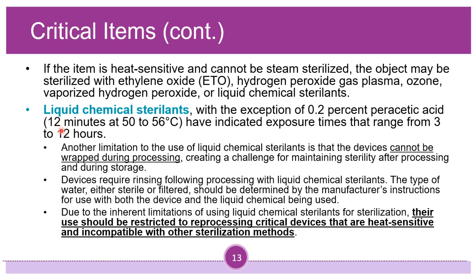Due to the inherent limitations of using liquid chemical sterilants for sterilization, their use should be restricted to reprocessing critical devices that are heat sensitive and incompatible with other sterilization methods. So, key takeaway here is you only want to use liquid chemical sterilants if it is absolutely necessary and you cannot use any other type of method, because there are so many limitations to ensuring sterility, and that's the real problem. It's difficult to ensure sterility when you are dealing with liquid chemical sterilants.